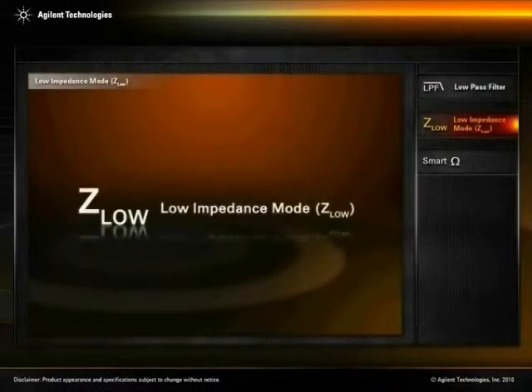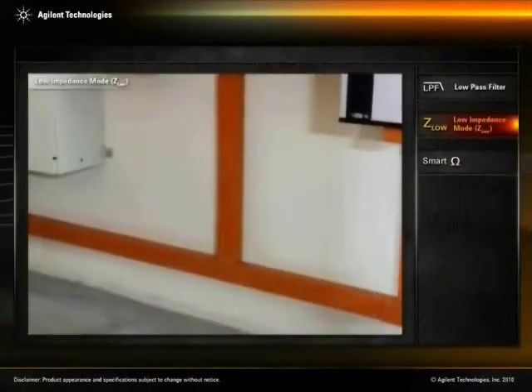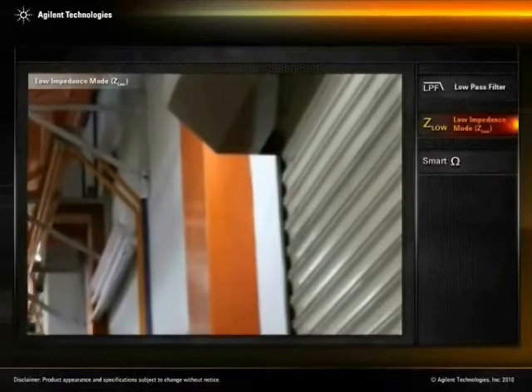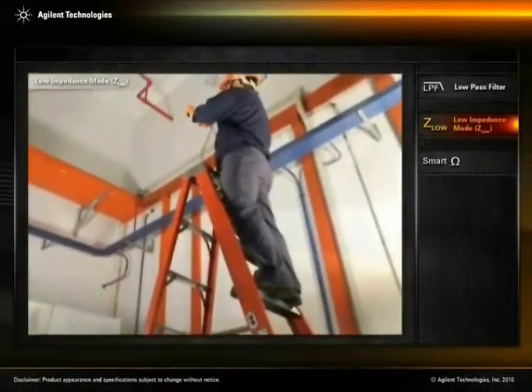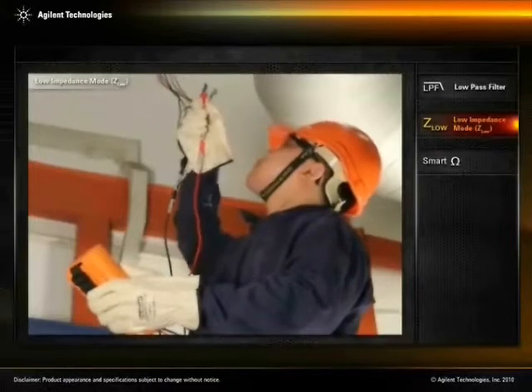Low-impedance mode, Z-Low. Electrical conduit is commonly found in many buildings. They protect enclosed conductors from moisture, chemical vapors, and impact. Although the conduit is safe and convenient, high-input impedance multimeters can pick up stray voltages on unused wires that run parallel with energized wiring.